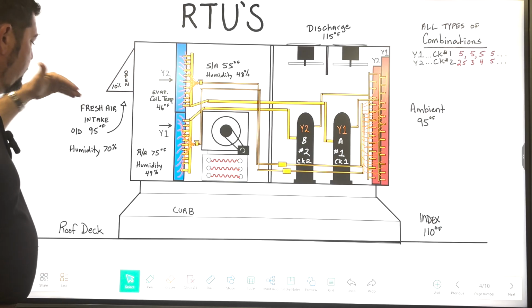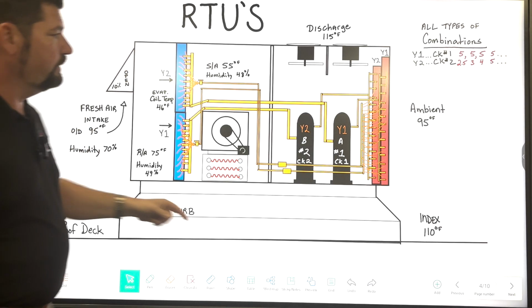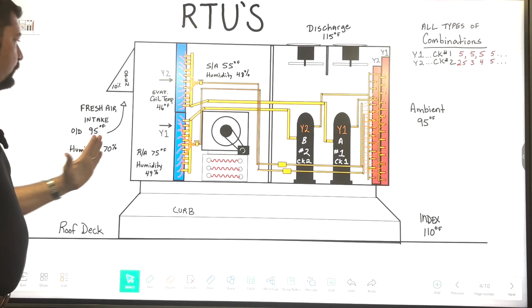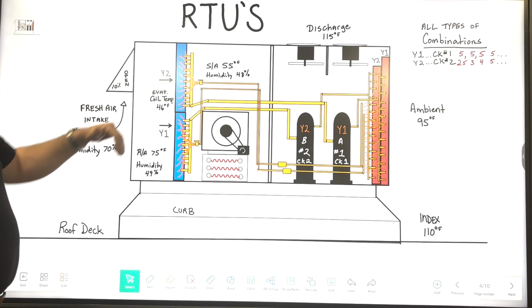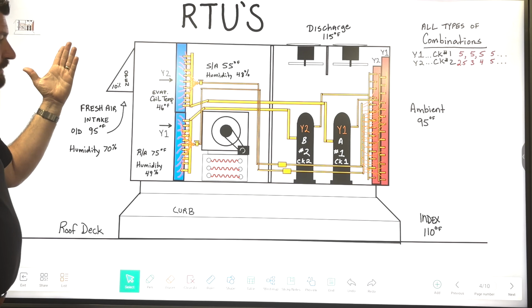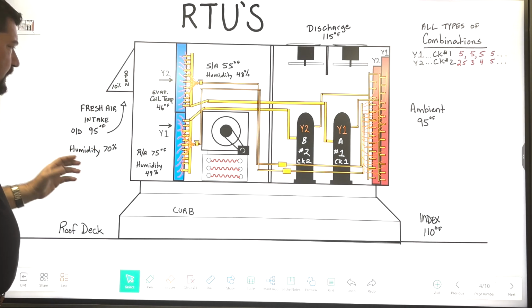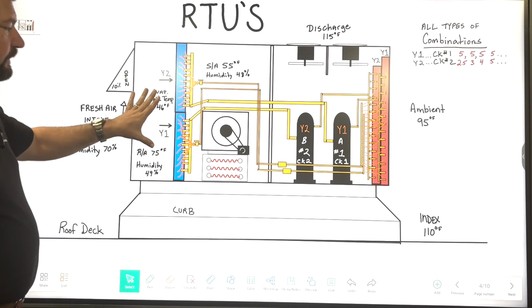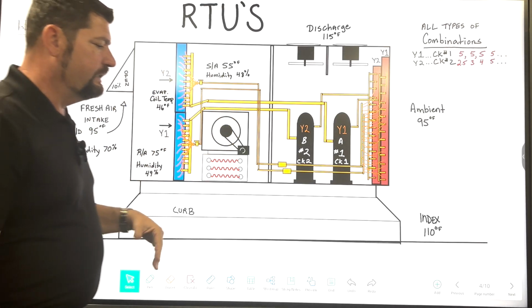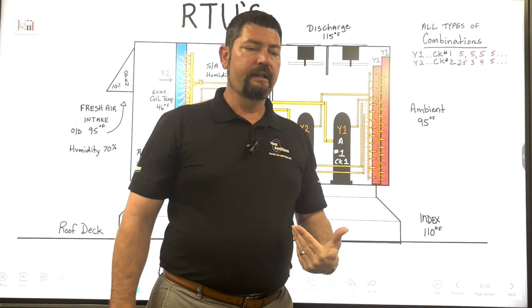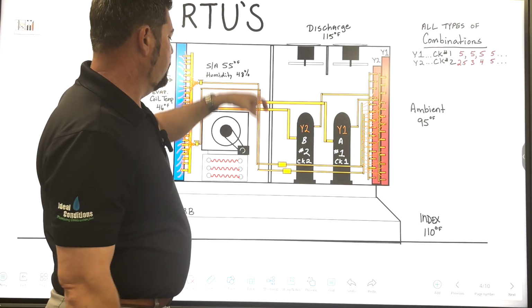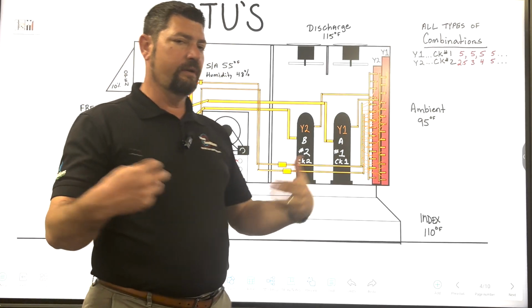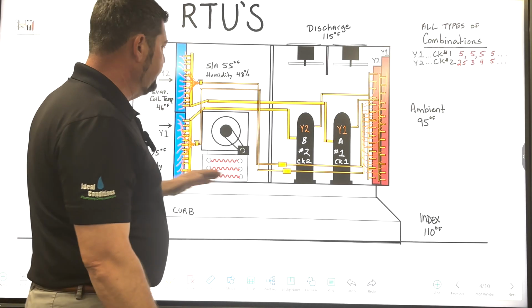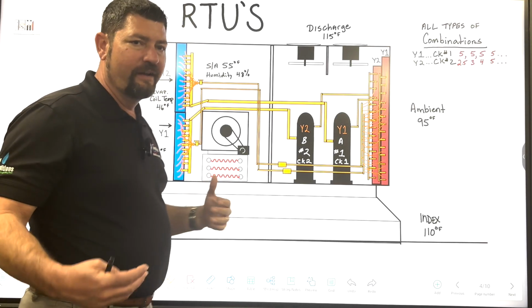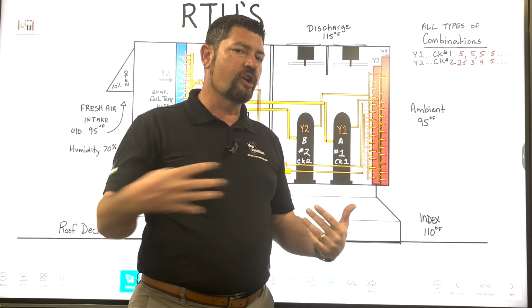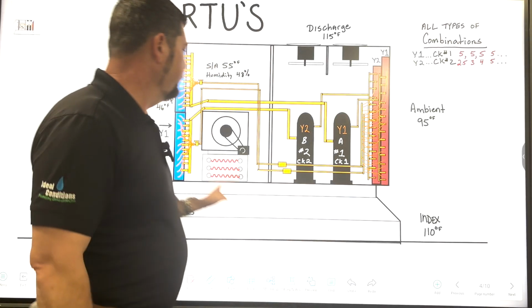I do have a fresh air damper. I just put the same 95-degree outdoor ambient temperature that we have. If that's pulling in across that fresh air, I put down here open at 10% or less, right? You don't really need to open them up too much because this whole entire blower cavity is in a negative pressure, right? And so with that, it's leaking air, right, all over the place. So it's already pulling in outside air, but as it leaks air all over the place, it's not leaking air in the correct direction. You're not pulling that air across your evaporator coil. You're pulling it all over the place.